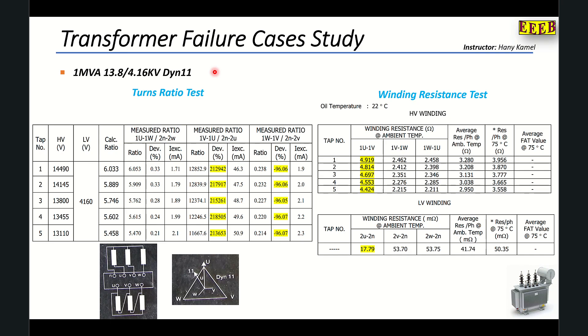Our test subject is a 1MVA transformer, 13.8 over 4.16 kV, vector group Dyn11. Now we are performing a turns ratio test. This shows the 5 taps on the HV side, the voltage as per the transformer nameplate, and this is the LV voltage. Here is the calculated ratio at each tap. The measured ratio shown is between 1U1W and 2N2W.